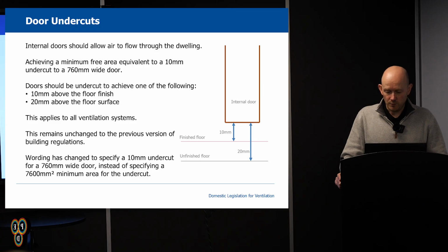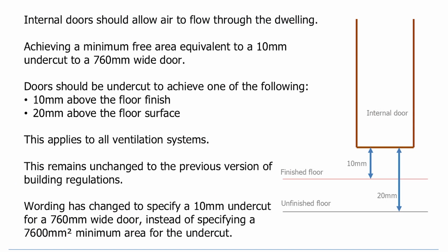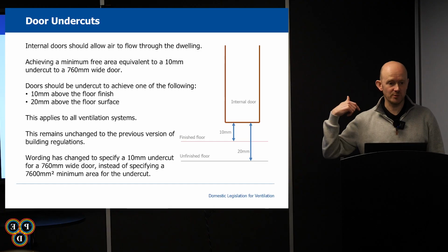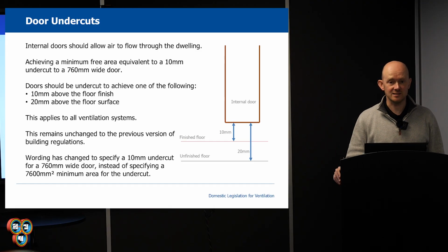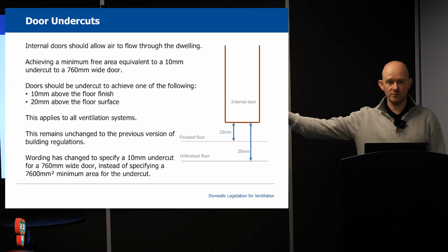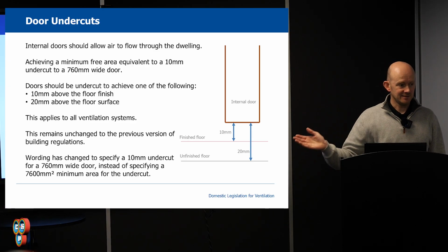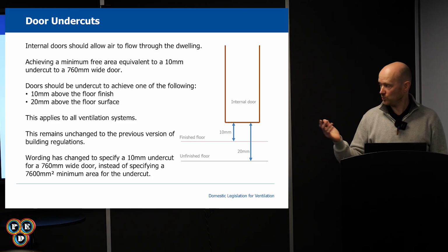All internal doors should allow airflow through the dwelling. The requirement is that it needs to be a free air equivalent of a 10 millimetre undercut to a 760 wide door. How many new builds have you gone in where they've put carpets in and they're touching the bottom of the door? 10 mil undercut to the finished floor, 20 mil undercut to the unfinished floor. But developers have to be careful, because if you're putting a whole ducted system in and it can't allow flow between the 2 rooms, you could get problems. The reality is the homeowner living there will fling a door open, walk through that room to another room and the door will stay open. But if they're all shut, it could cause problems, and that's what they're saying.